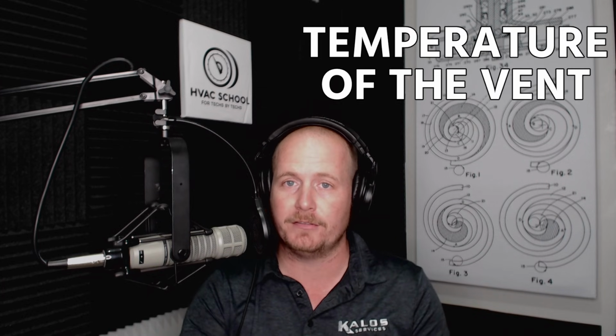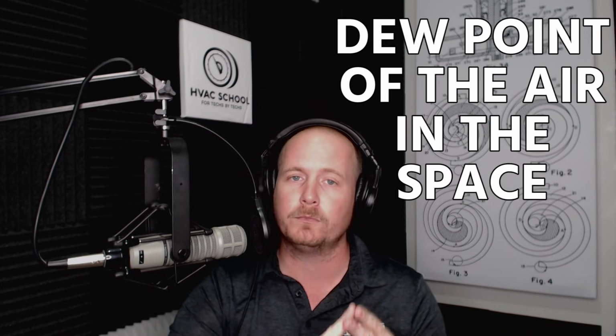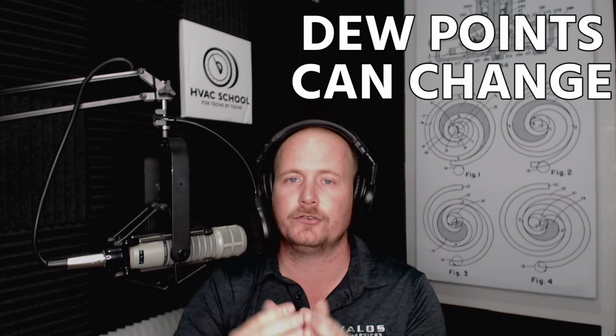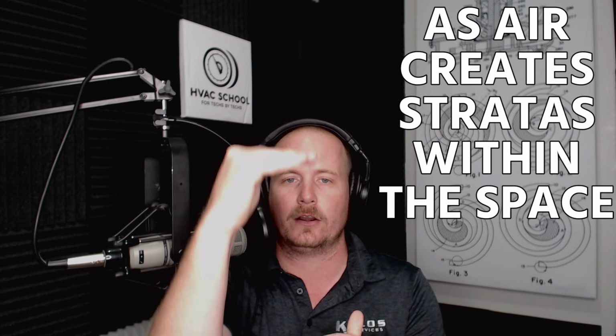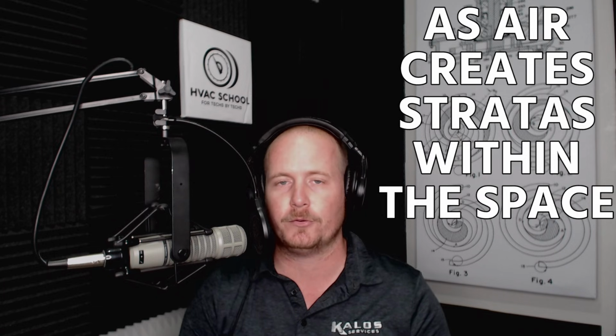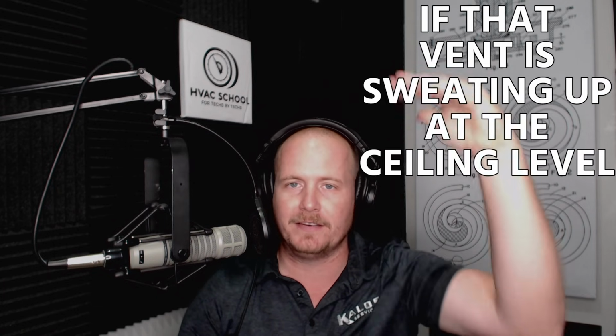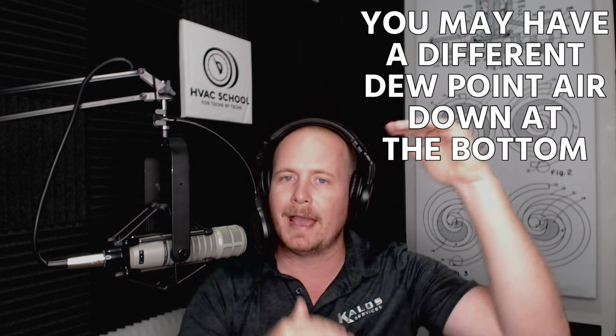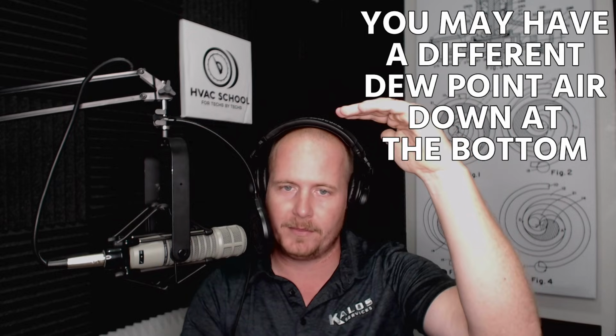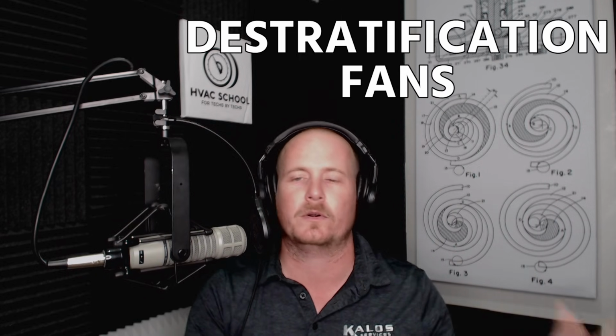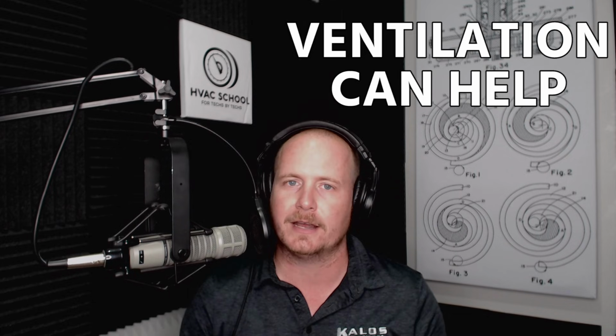If that is already taken care of and you don't have issues with moist air intrusion around it, well, now you have to think about the temperature of the vent and you have to think about the dew point of the air in the space. First thing to remember is that dew points can change as that air creates strata within a space. So if you have a really, really high ceiling and that vent is sweating up at the ceiling level, you may have a different dew point air down at the bottom. And that's something that sometimes you can solve with things like destratification fans in order to help mix that air. So ventilation can help in some situations.